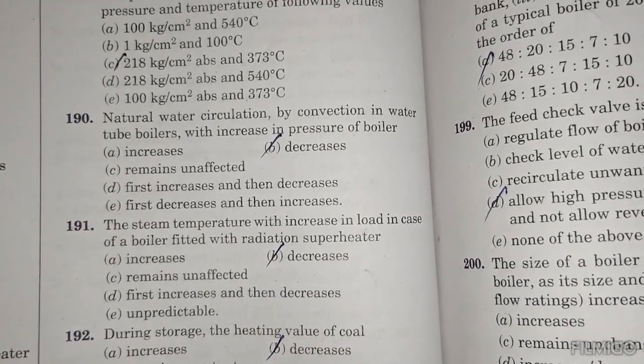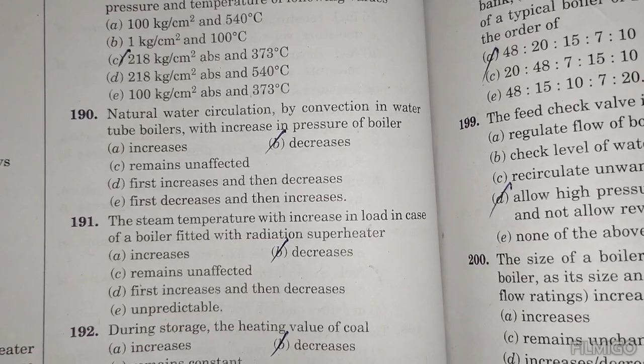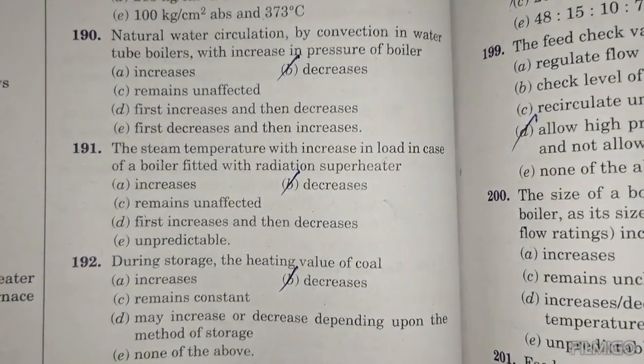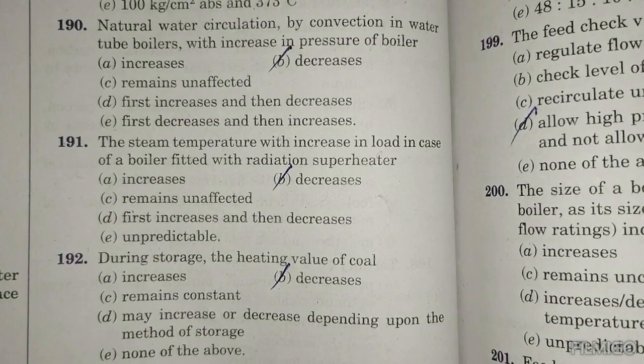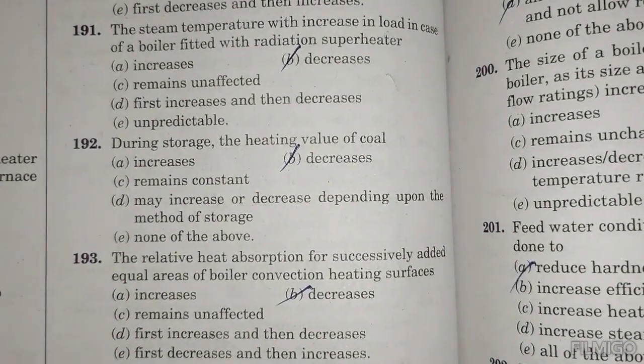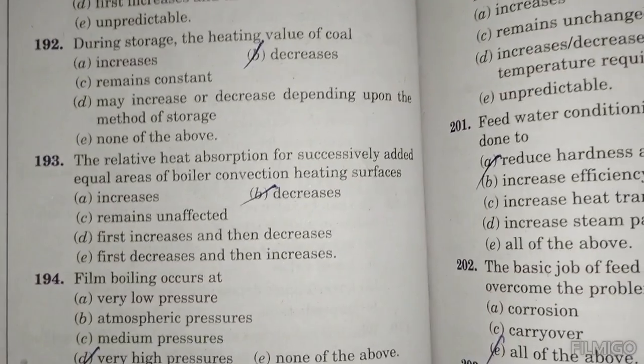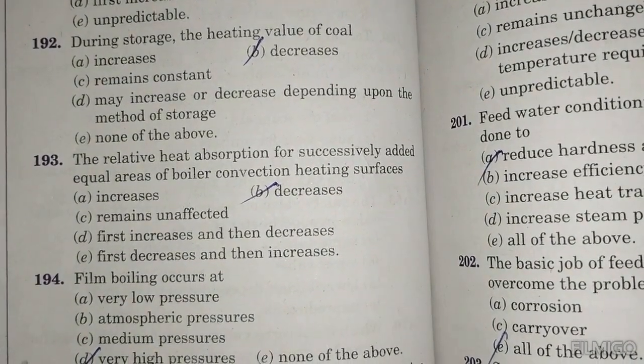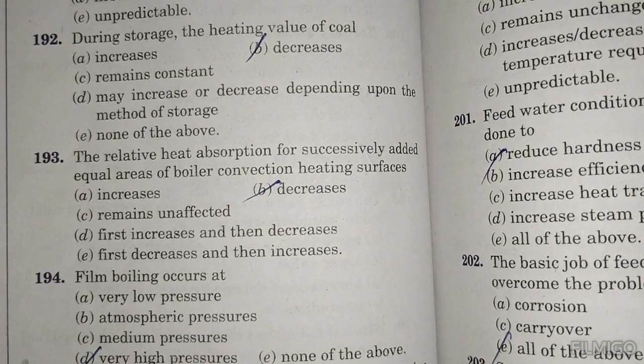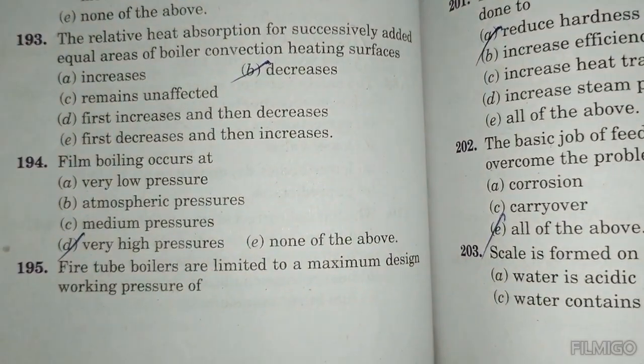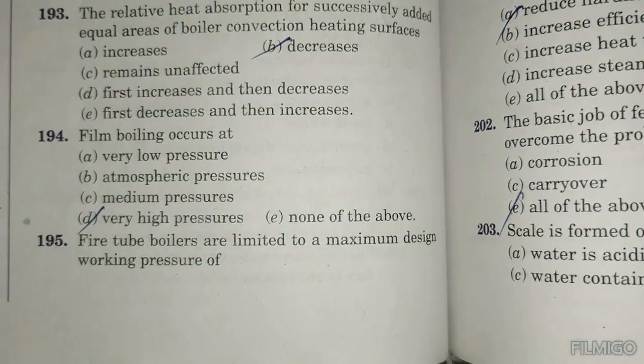Natural water circulation by convection in water tube boilers decreases with increases in the pressure of the boiler. The steam temperature with increases in load in a boiler fitted with radiant superheater decreases. During storage the heating value of coal decreases. The relative heat absorption for successively added equal areas of boiler convection heating surface decreases. Film boiling occurs at very high pressure.